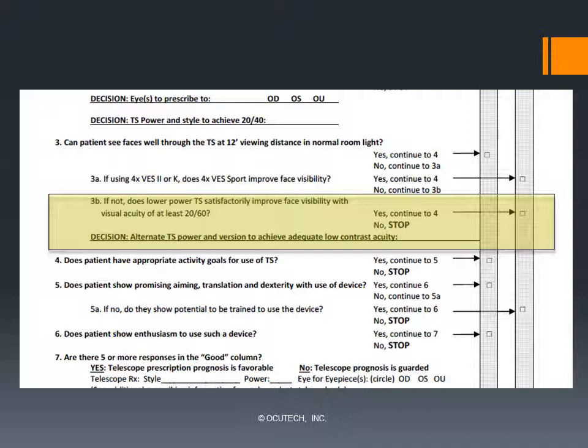If contrast through the telescope remains insufficient, you can also try a lower power telescope. The lower the power, the brighter the image will be; however, this will be at the expense of reduced acuity through the device. If, while using a lower power device, your patient can now see faces adequately from across the room despite the lower acuity of at least 20/60, check the 3B box in the fair column. Enter any changes to the telescope style or power you are considering, and move on to question 4. If your patient still cannot see faces well, you may either choose to discontinue the assessment or suggest that the bioptic may be of most benefit when used in brightly lit and outdoor environments.